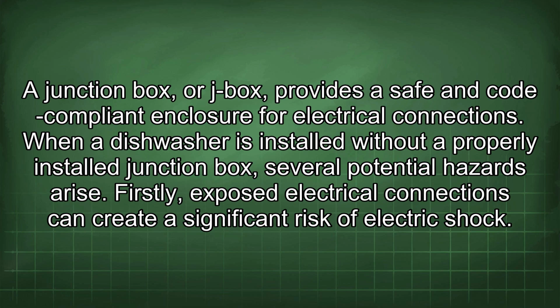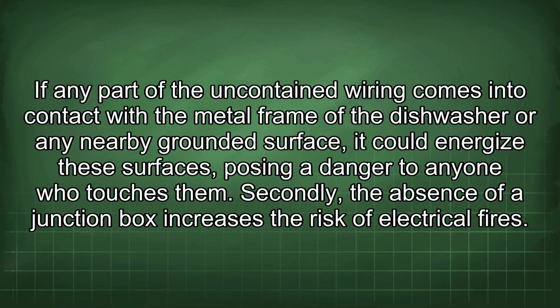When a dishwasher is installed without a properly installed junction box, several potential hazards arise. Firstly, exposed electrical connections can create a significant risk of electric shock. If any part of the uncontained wiring comes into contact with the metal frame of the dishwasher or any nearby grounded surface, it could energize these surfaces, posing a danger to anyone who touches them.